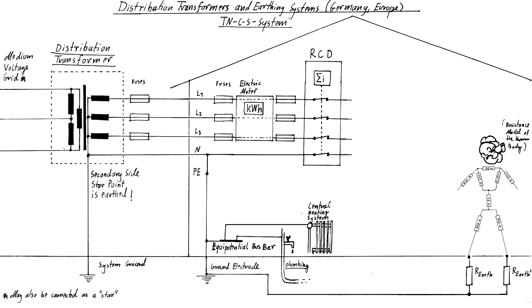Now let's see what kind of safety mechanisms are existent in this system. First of all, we have a range of fuses on the way from the transformer secondary to the load. These fuses can also be modern circuit breakers, but the physical principle behind their operation is not so much of interest right now. More interesting is in which way they act as safety measures.